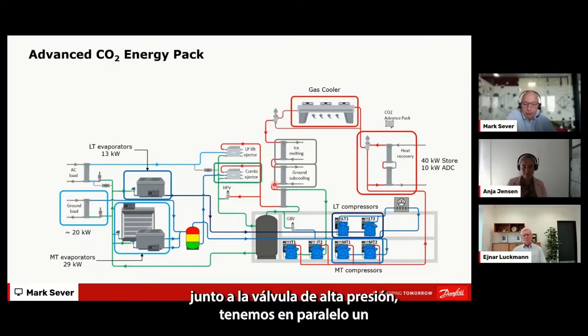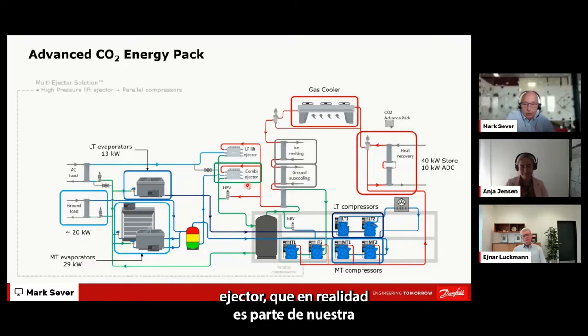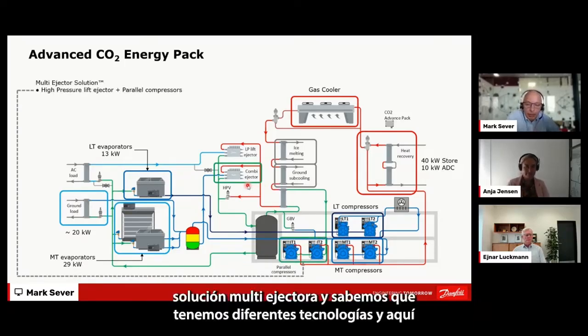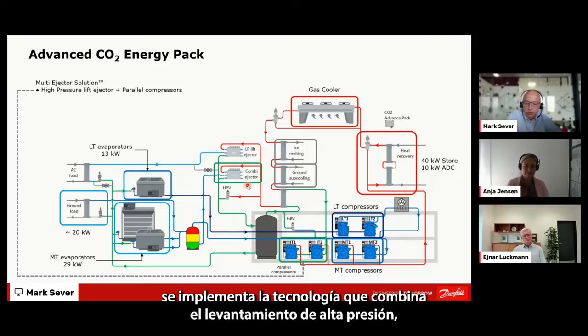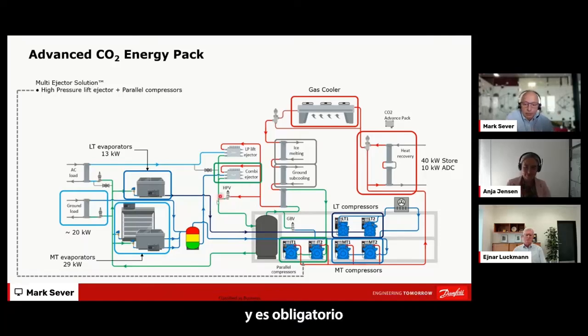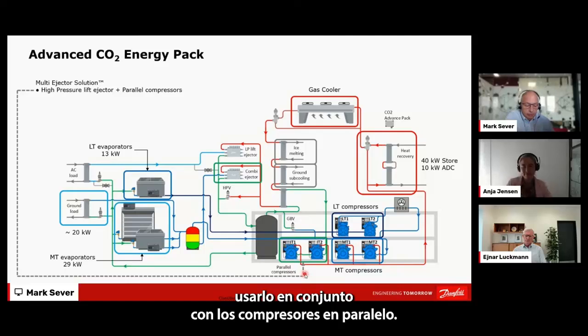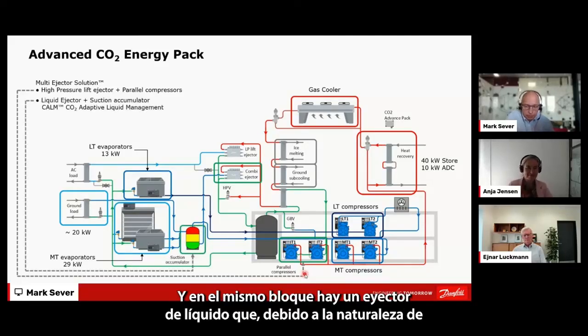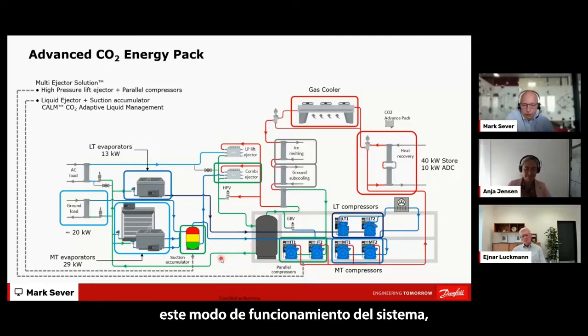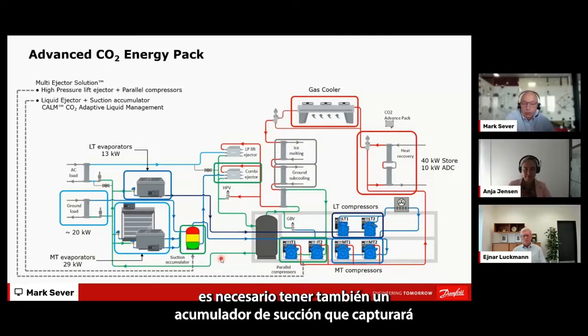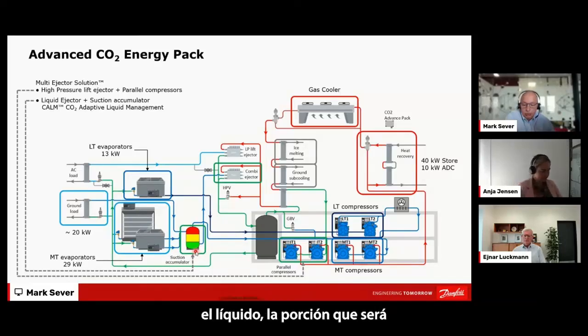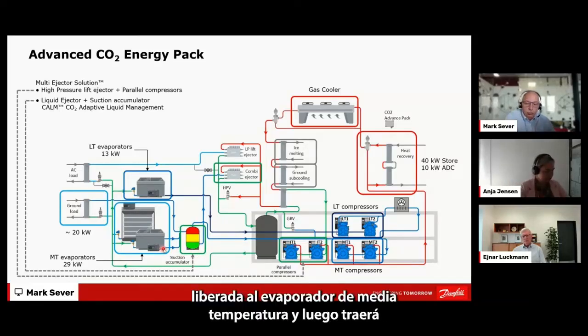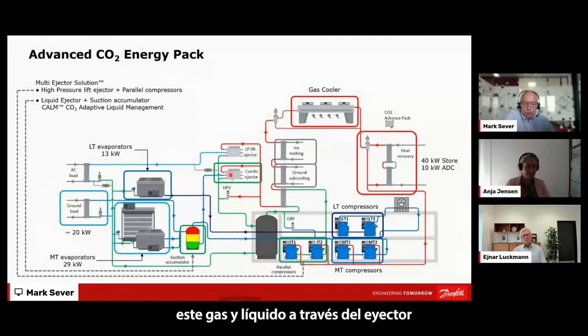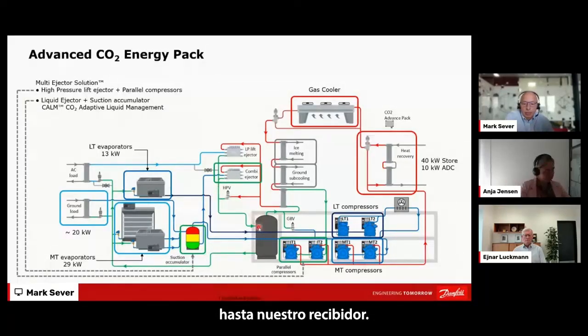Then together with the high pressure valve, we have in parallel a combi ejector, which is part of our multi-ejector solution. We have different technologies, and here we implemented a combination of a high pressure lift ejector, which is mandatory to be used together with the parallel compressors. In the same block there is a liquid ejector, which, because of the nature of this system's mode of operation, needs a suction accumulator that captures the liquid portion released from the medium temperature evaporators, and then brings this gas and liquid through the ejector to our receiver.